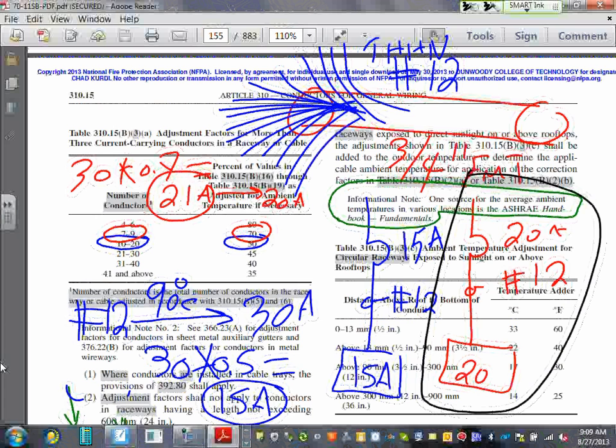Comments, questions about the derating based on bundling? Bundling means grouping the conductors. Who cares? When you are working for electrical contractors and electrical engineers, electrical engineers don't care much about bundling, but electrical contractors do. When you come out of this panel, do you think you would put an EMT conduit for every circuit? If you had a neutral EMT conduit with each, you would be completely shocked. When they come out of this panel, they come up with multiple 3/4 inch.